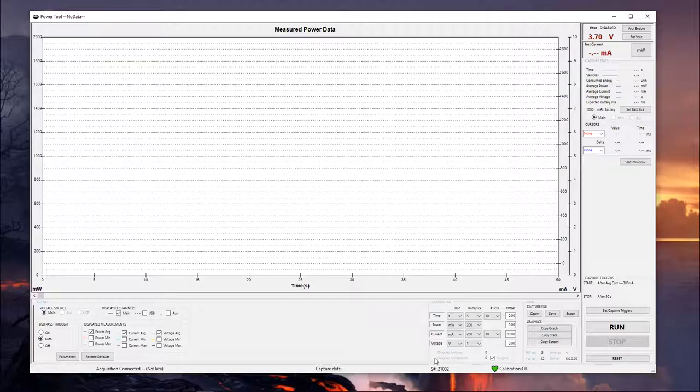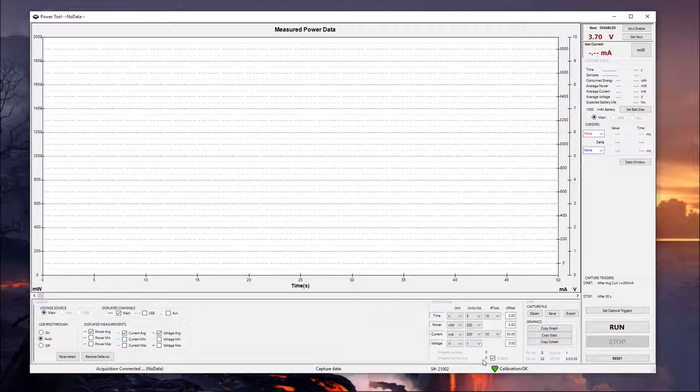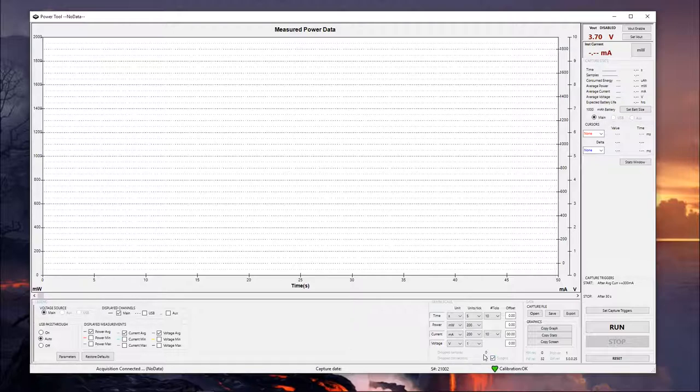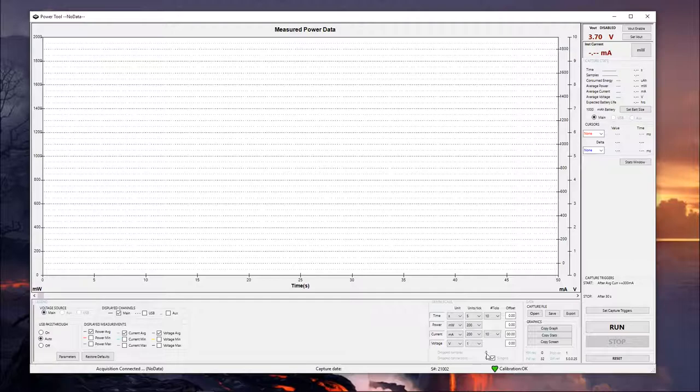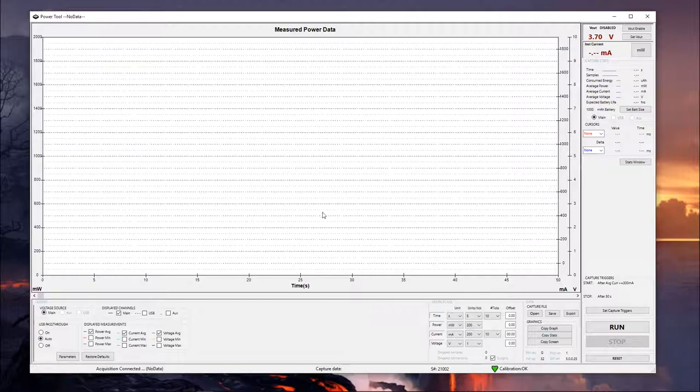Below that, we've got our drop samples and dropped connections. So if for whatever reason your power monitor drops its USB connection during a test and then reconnects automatically, you're going to see that number here. It will typically stay zero, and the drop samples should also be a fairly low number. If you're seeing a very large value here, it could indicate some other issue going on, particularly if it's sitting at 65,535. That's the maximum value allowed for this. If you're seeing that, odds are you're dropping way more samples than that, and it's going to cause a lot of different issues.